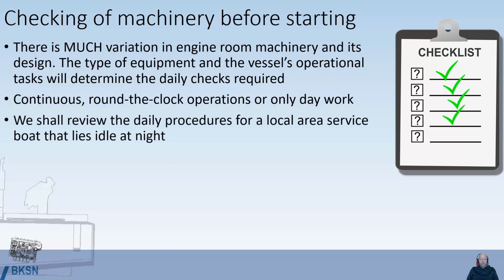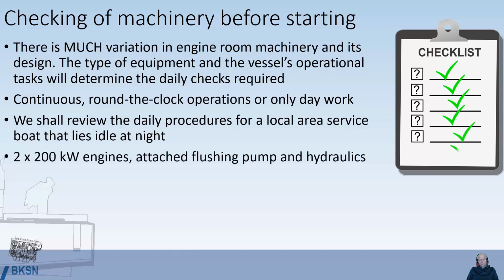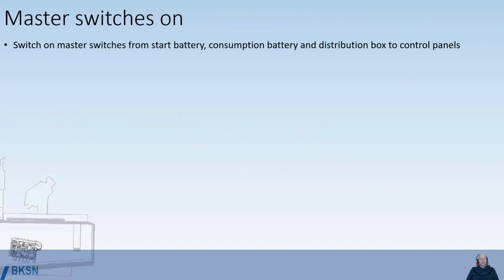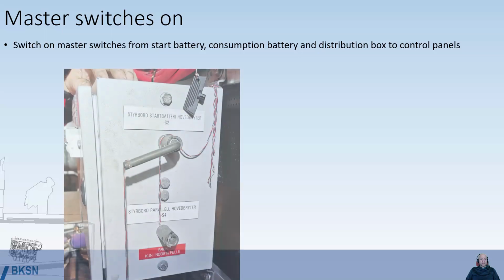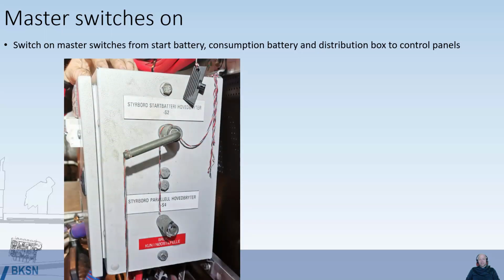We're going to have a quick look at the daily procedures for a daily operation service vessel from the fish farming industry, which is idle at night. This vessel is equipped with two 200 kilowatt propulsion engines with an attached flushing pump and hydraulics also attached to the main engines. Daily routines, you start out with switching on the master switches from the starting batteries, consumption battery and the distribution box to the different control panels and electrical distribution panels. On with that.